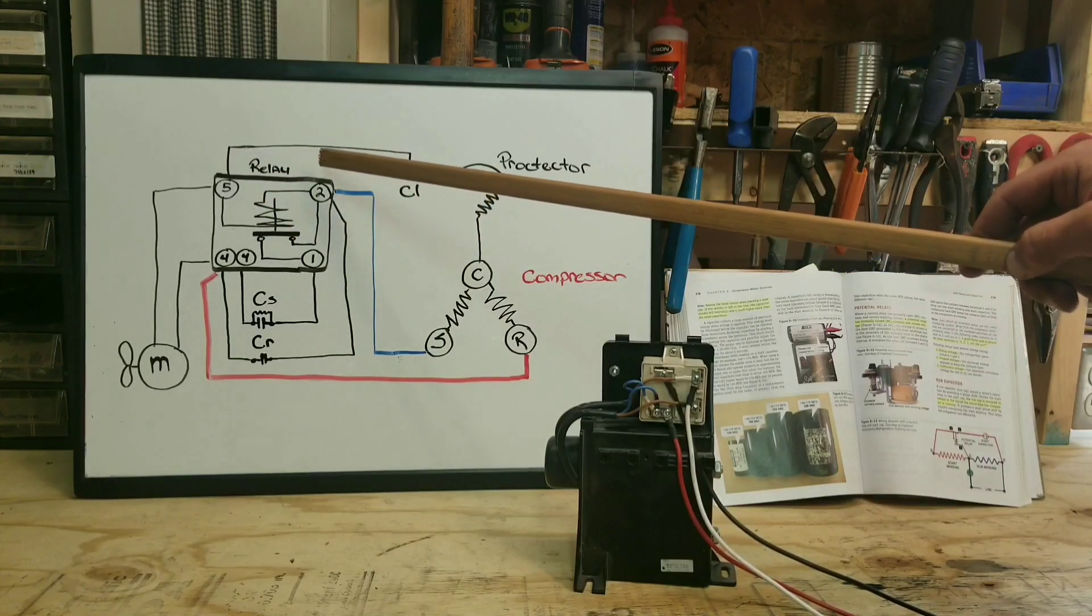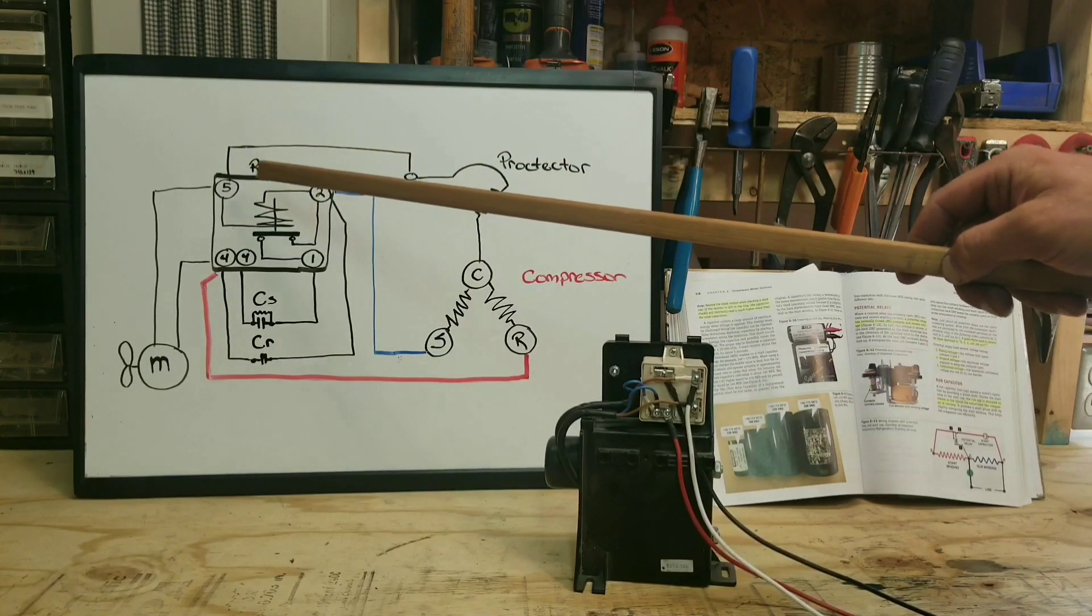All right guys, so that wraps up our little speech about potential relays. One of the things I did want to reiterate that I don't think I touched on in the video is that sometimes that back EMF voltage coming off of the start winding can be upwards of 400 volts. So be very careful if you are testing it. If you feel like you just want to go in there and poke around with your meter leads, be very careful because you could be touching some pretty high voltage, even though you're only working on a 120, 208, 240, whatever unit. That back EMF coming off of that start winding might be much, much higher, so be careful with that.